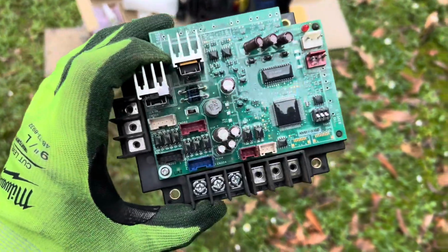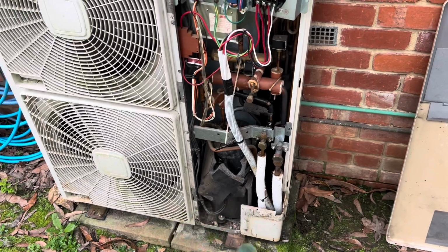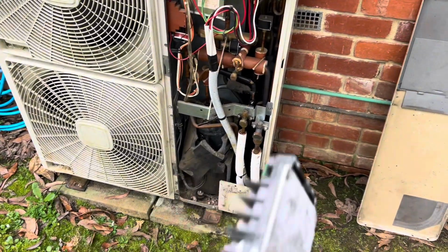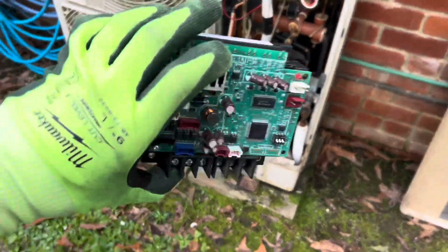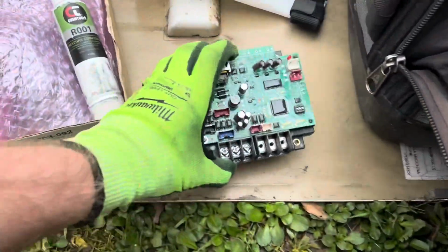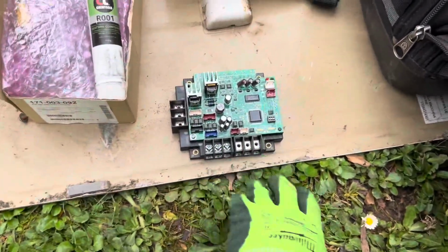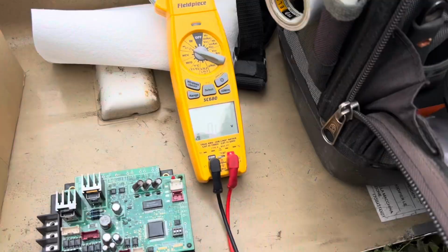Like I said, they said the drive on this was faulty. I obviously tested the compressor electrically, which tested out fine, so it could be seized. I took a gamble and said it wasn't, and I'll show you how I went about testing this.